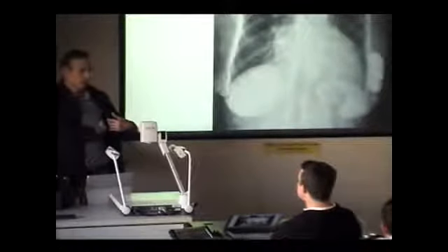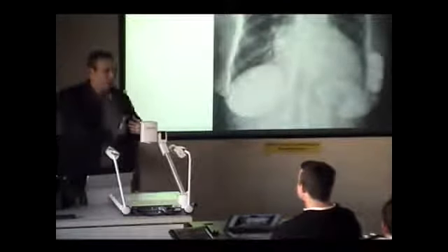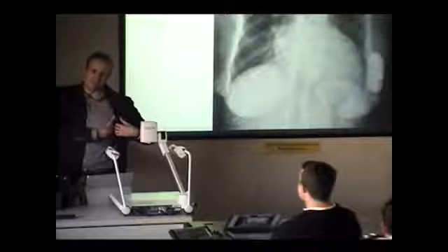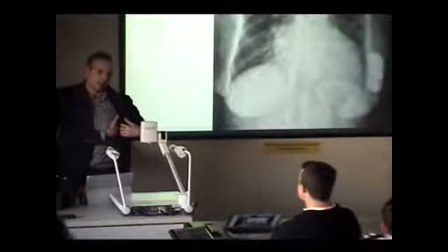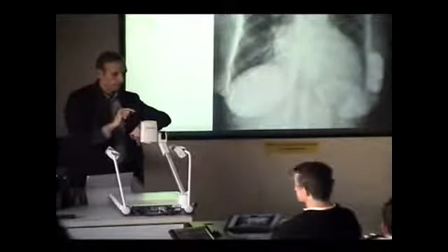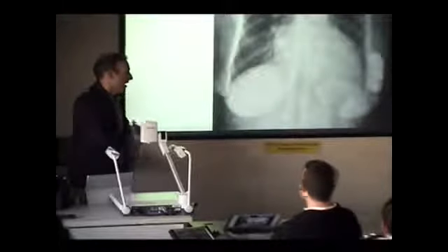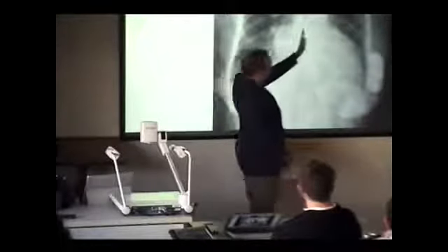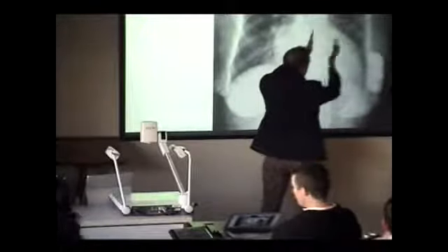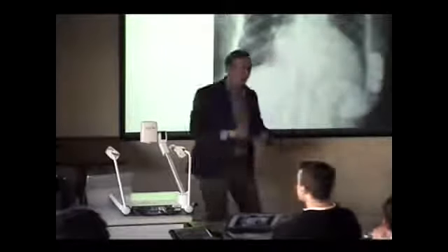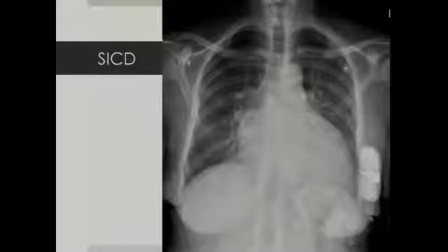So you're just along the side of the rib, really kind of behind, as deep as we can, in the armpit. So it allows us to get the zone of defibrillation from here to here. So you're sandwiching the ventricle. That's why we need that can, but really far back. That's made by Boston Scientific currently.